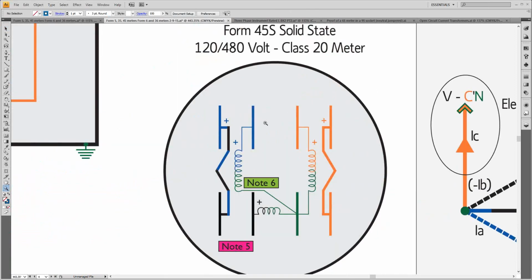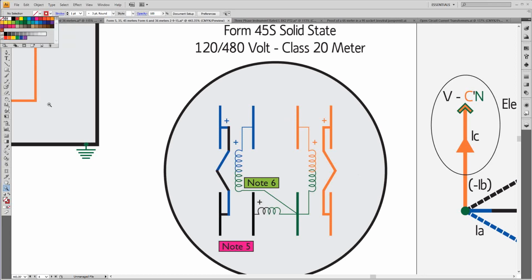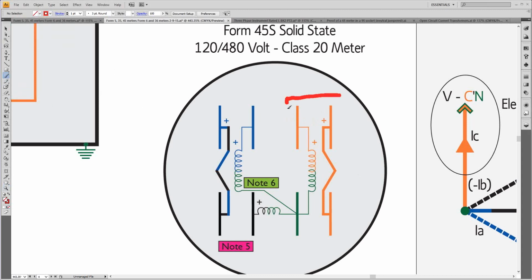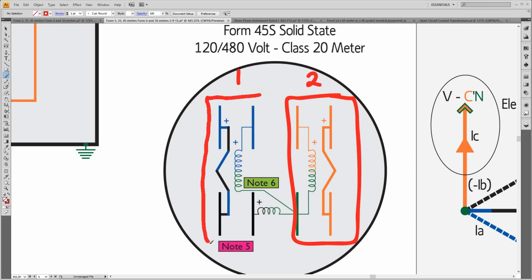So the 2-element meter here, as I look at the elements on this one, I'll get my red pen again. The right-hand side element, this element, is exactly the same in all 3 meters. Phase neutral, high leg voltage, and IC current flowing through that element. So this is element number 2. For element number 1 now, again, includes that connection there. Element number 2 has, in the 45S, 2 potential coils.